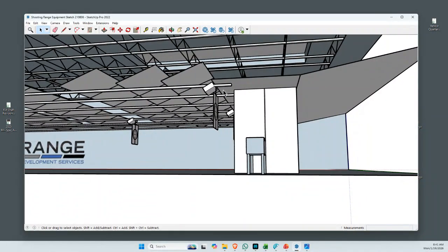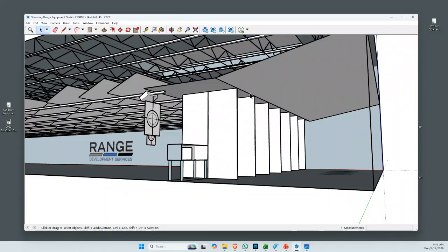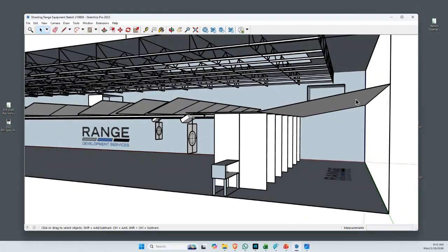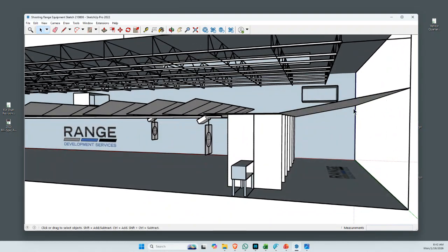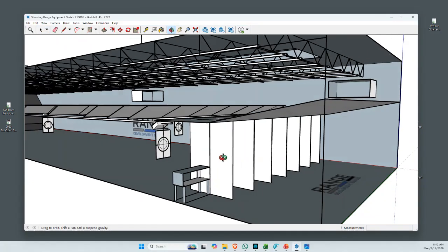The safety ceiling goes really above and downrange a little bit. It goes above the stall walls. And then from the stall walls at the back edge back to the diffuser is just a normal office grid system. Sometimes it gets a little bit more fancy if you want to have a different kind of ceiling structure. But what it's doing is not letting air go out of that diffuser and just get pushed up. All the air needs to be pushed and focused past the firing line. So that's why this angled ceiling structure is designed the way that it is, because that radial diffuser will push it. The ceiling will guide that air through the firing line space between the stall walls. Okay.